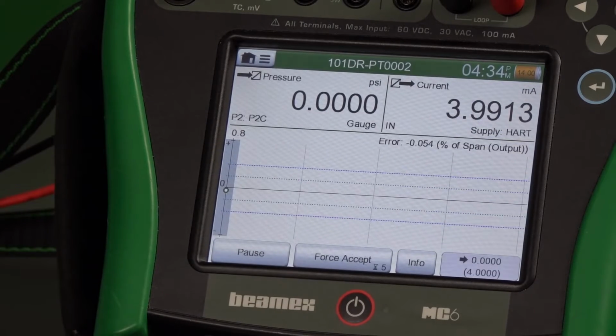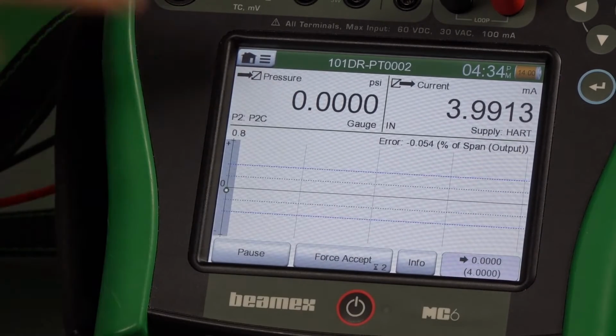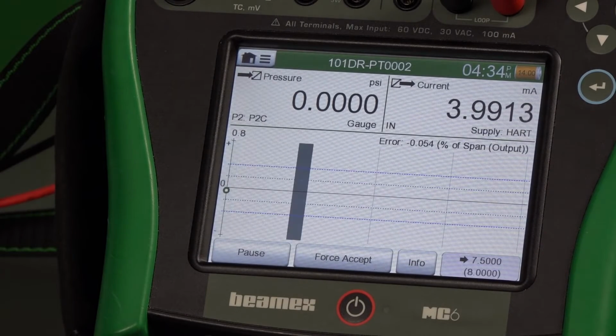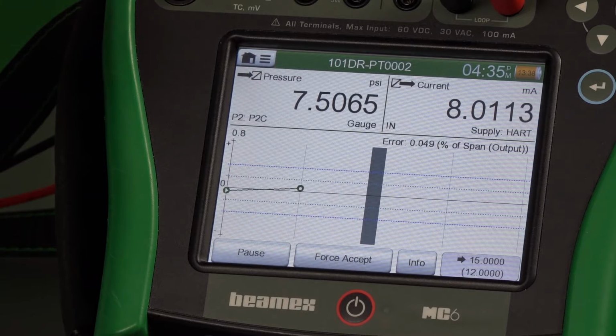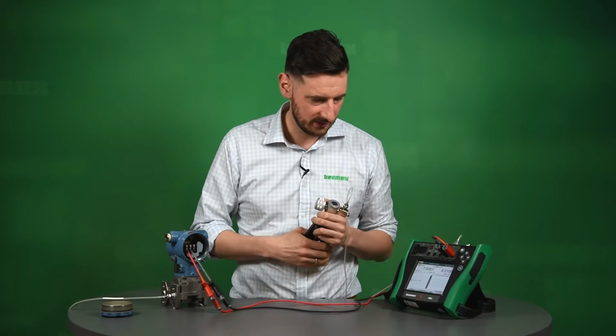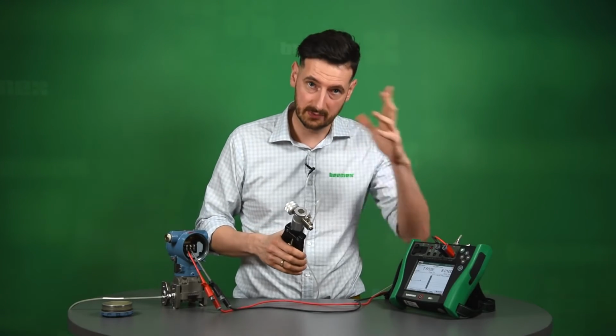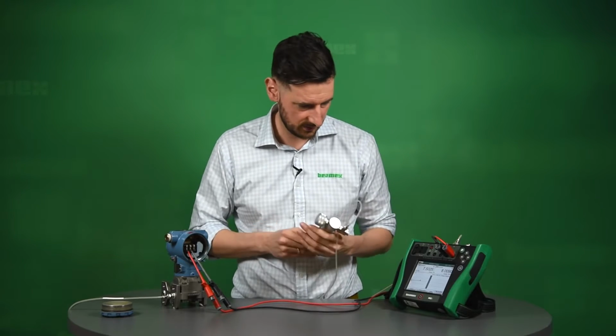Okay, we're ready to start. So the first calibration point is 0 and 4 milliamps. So don't forget, we're going to do 5 up and 5 down. Right now, it's going to ask us to go to 7.5. So let's do that now. So let's go to more or less 7.5. We don't have to be exactly precise, but what we have to do is obviously keep it stable, keep it as close as possible to that 7.5, and then we wait until the signal is stable, allowing us to save this calibration point and move on to the next one. So that's what we're going to do.